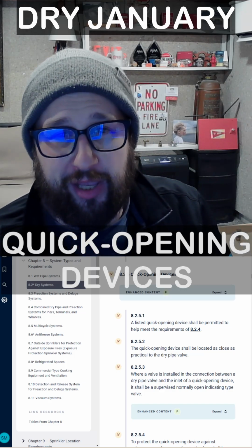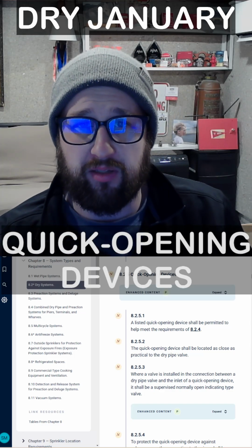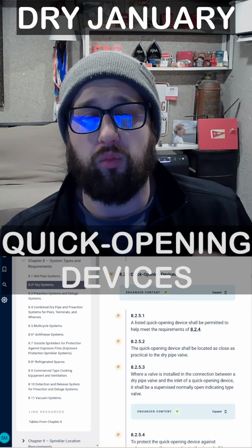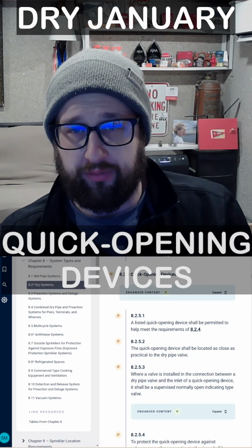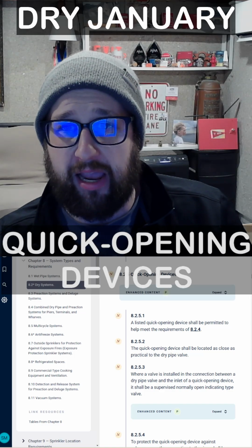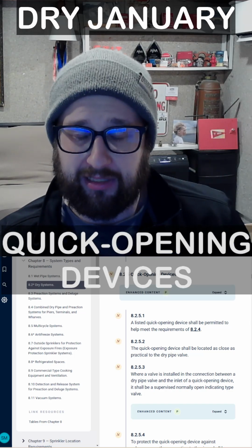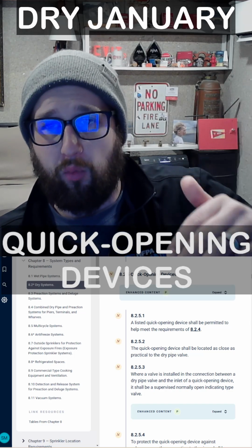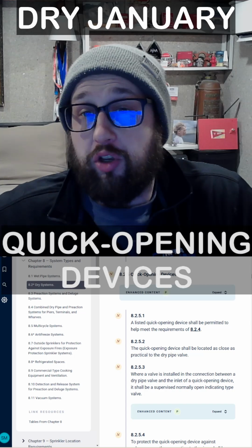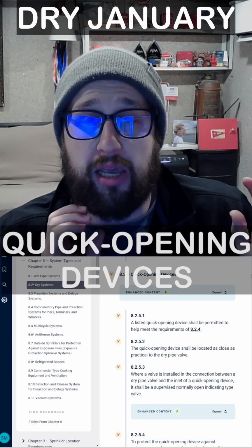So for the last video of dry January, I'm going to be talking about quick opening devices. Now with a dry sprinkler system, one thing that's important is water delivery time. We know that it's going to take a certain amount of time to drain the pressurized air or nitrogen out of the system through the operated sprinkler to then activate the dry pipe valve and get water into the system and then out the sprinkler. So there are some things you could do to help speed up that water delivery. One thing is to use a quick opening device.